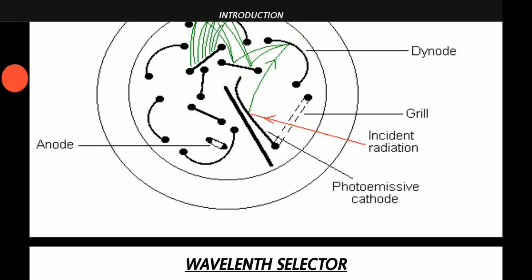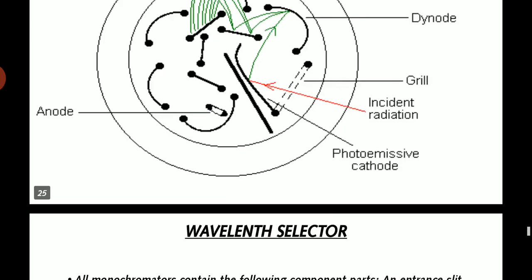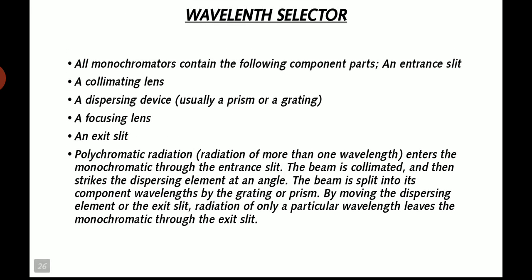Intense light can damage photomultipliers. This is the structure of the photomultiplier tube. In the center is a grille for incident radiation, then the photoemissive cathode, and the outer is a black colored dynode. In the center is a small form anode.